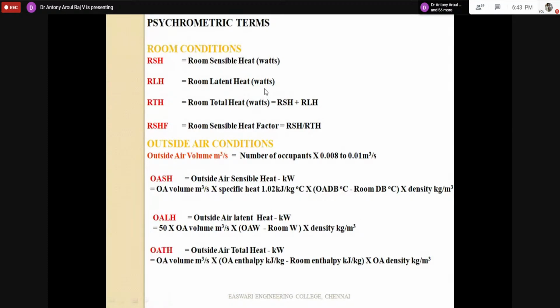The load pattern of the room will be based on the room sensible heat factor, the ratio of sensible heat to room total heat. That will tell you how much will be the latent heat and how much will be the sensible heat, which is useful for us to decide the cooling coil. If you have a high latent application, you will go for a very low ADP with more rows of coil. What are the other components of the load? Room total load is whatever load is there inside the room, the sensible and latent, and that is called the room total heat.